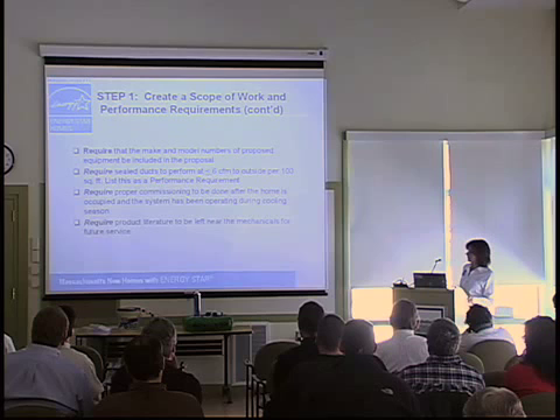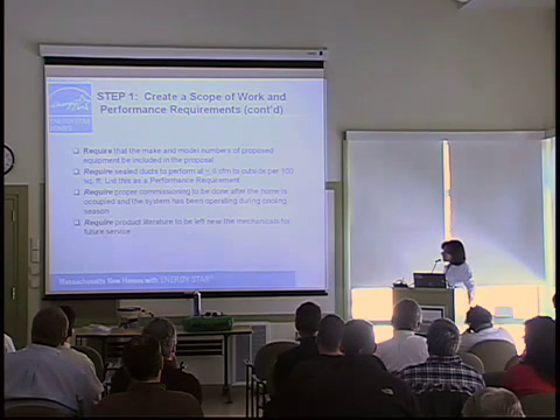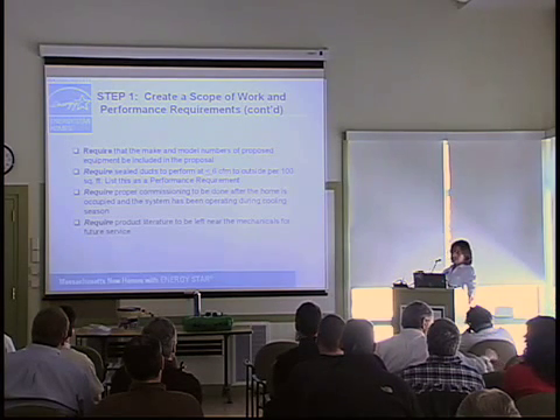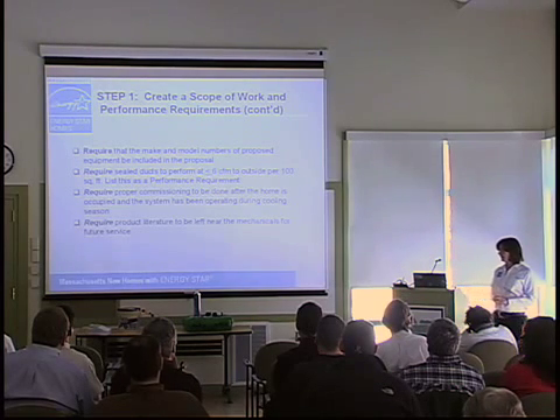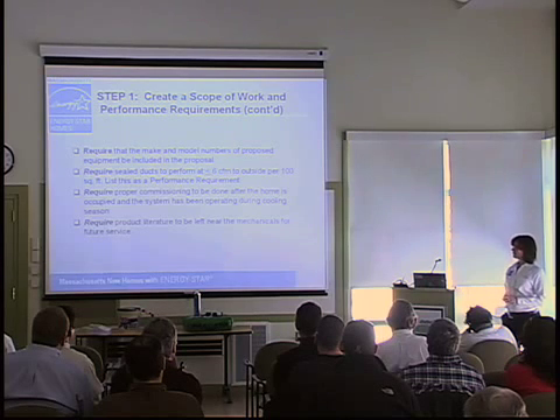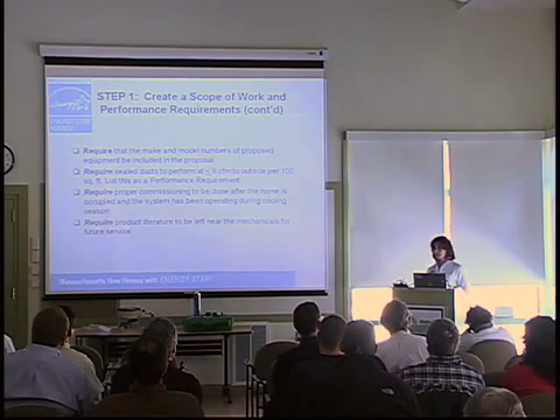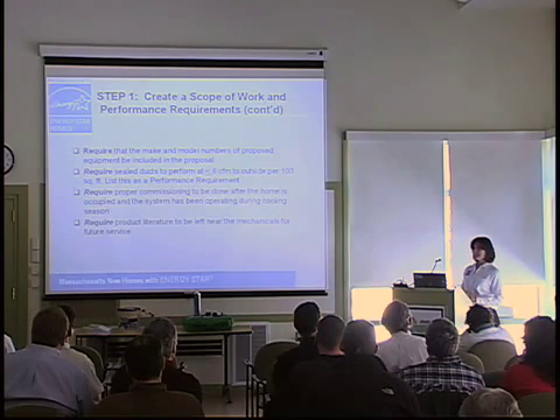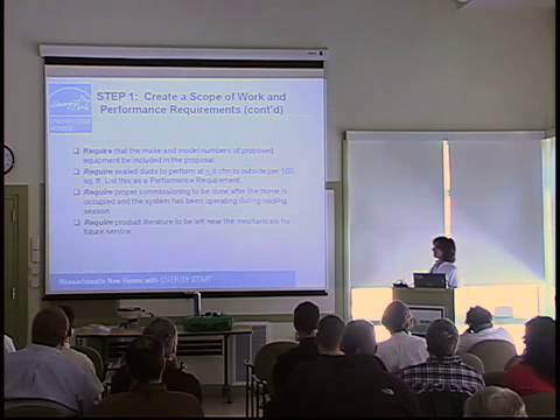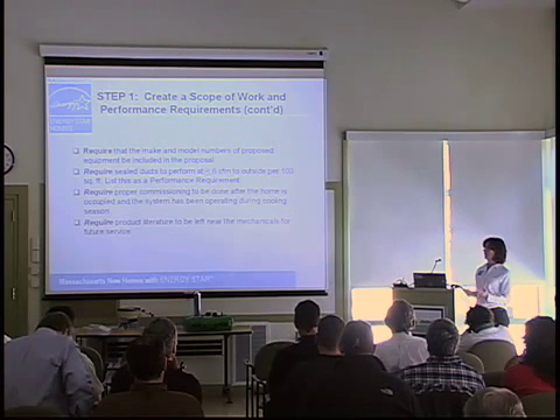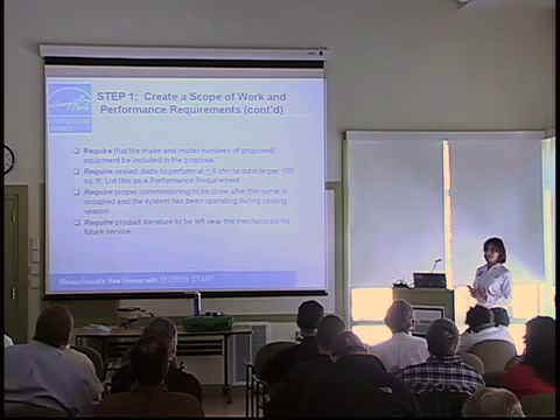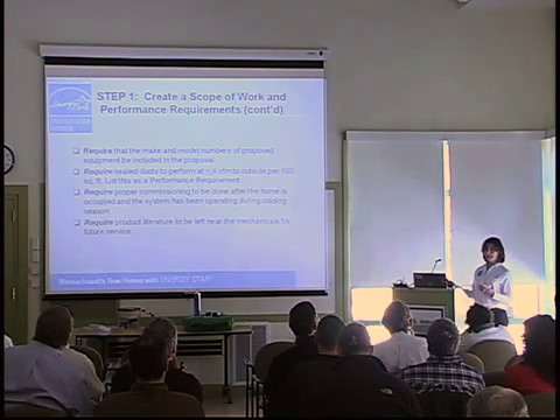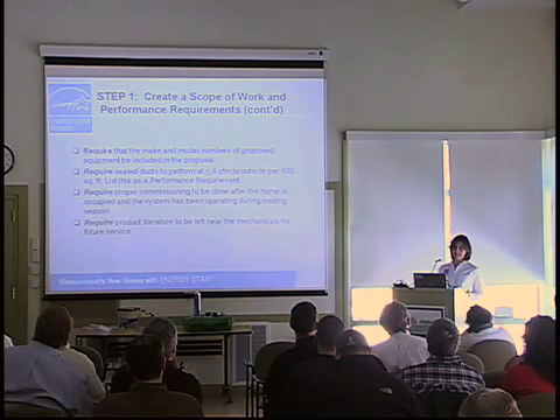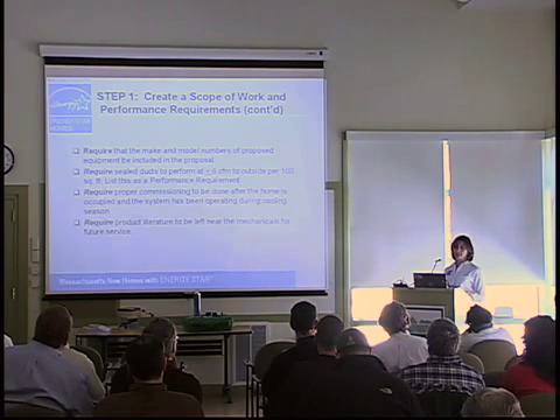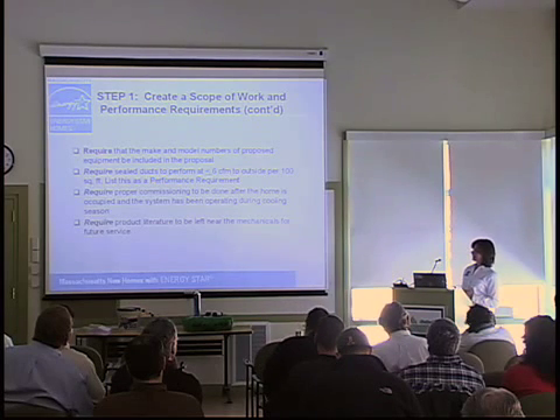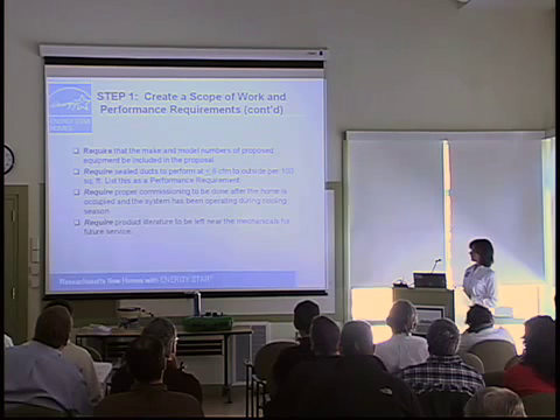You know that you're going to require your sealed ducts to perform at less than 6 CFMs to outside per 100 square feet. And one recommendation, you're an Energy Star builder. This means a lot to you. So require it as a performance requirement. Perhaps you might want to include it in your payment schedule. That may give the contractor more incentive to seal those ducts up properly, to make sure his crew knows how to seal the ducts up properly, and might prevent some extra time and money that you may have to spend in resealing, identifying places where you're maybe leaking and not passing your duct blower test, and then also having the rater come back and perform a second duct test. So maybe adjusting your payment terms to include that as a performance requirement might motivate the contractor to make sure they know what to do.